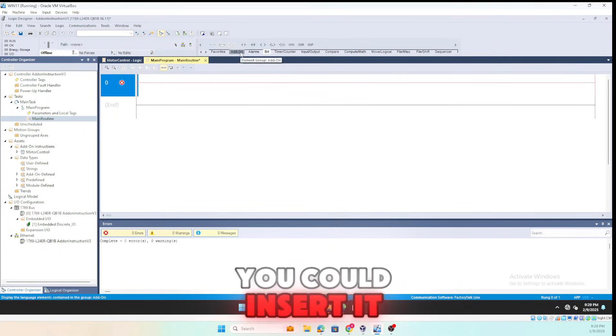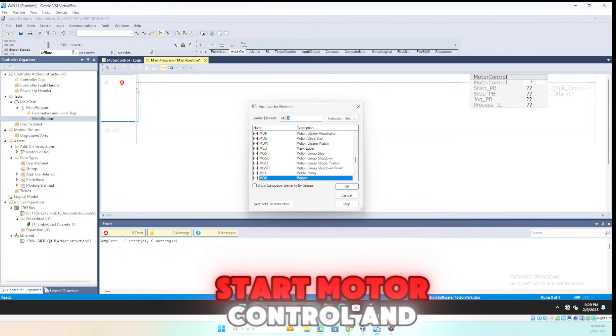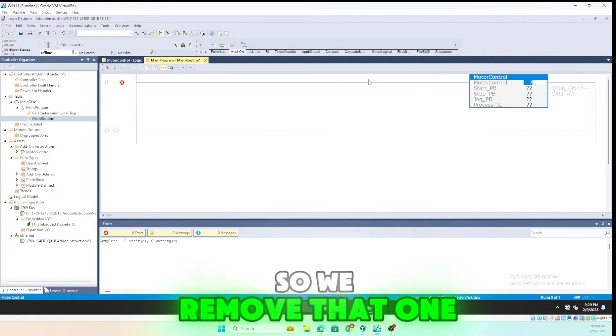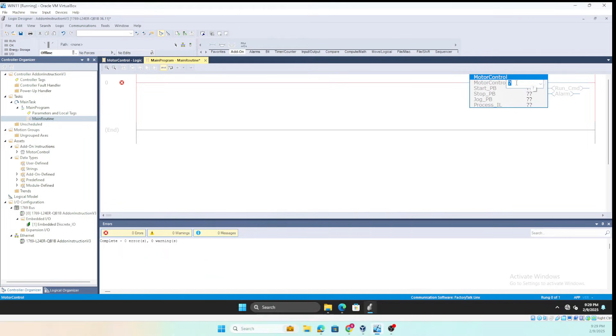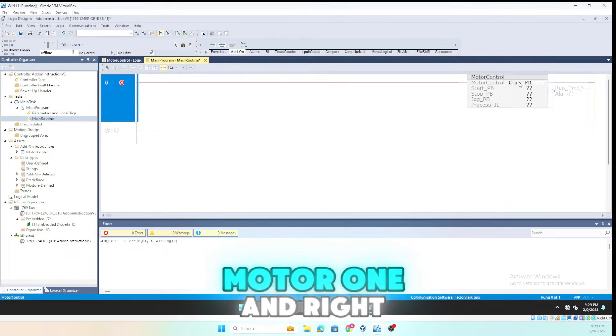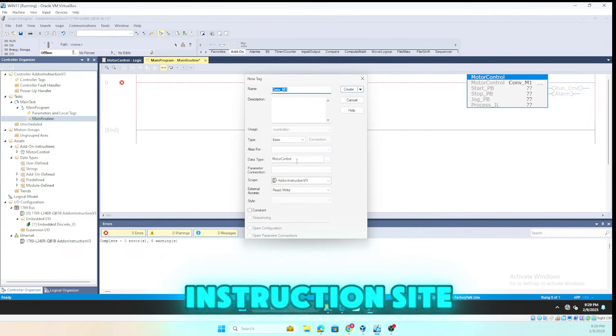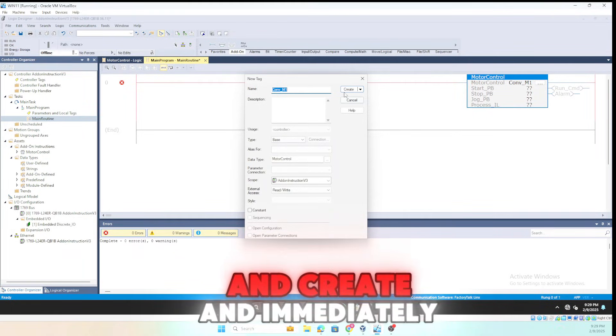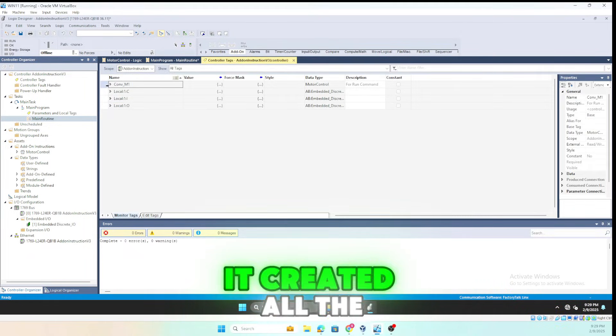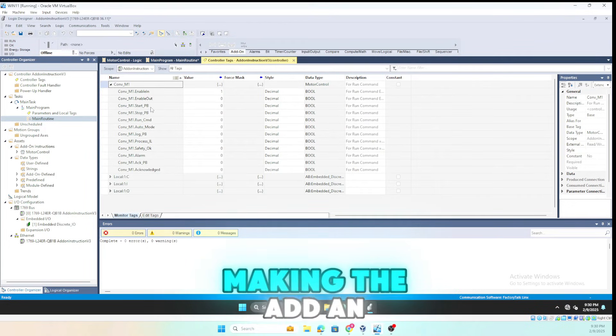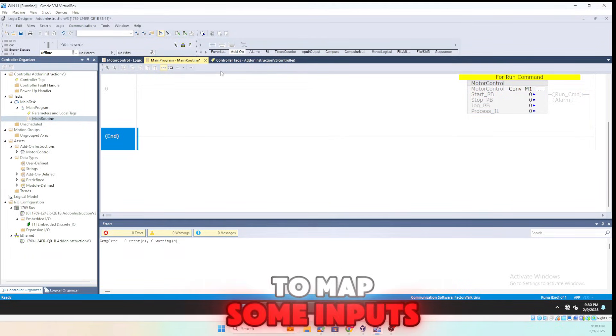To use the add-on instruction set, you can insert it from the add-on instruction set list or press the Insert key on your keyboard and search for motor control. Just like any other instruction such as a timer or CTD, you give it a name for the instance — we call it Conveyor_Motor_1. Right-click, create new tag, leave everything as default. Immediately after creating it, if you look at the monitor properties on Conveyor_M1, it created all the tags needed for the add-on instruction to work — start button, stop button, and run command.